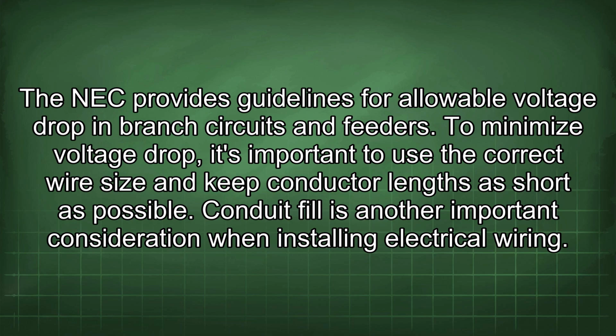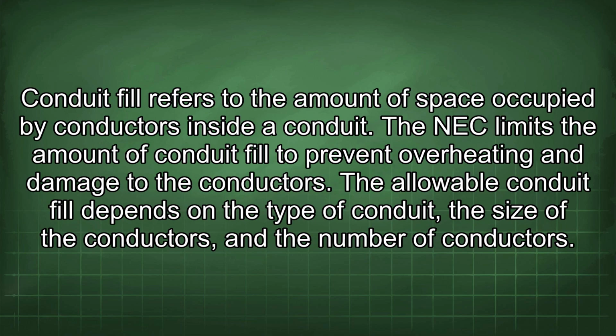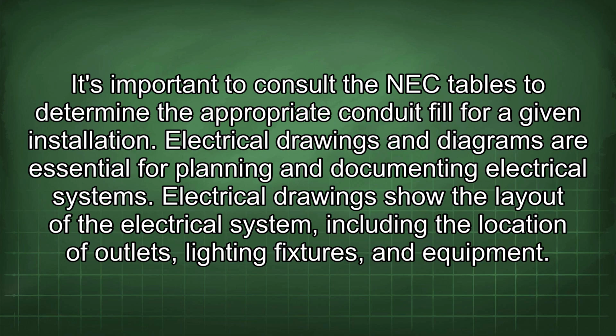Conduit fill is another important consideration when installing electrical wiring. Conduit fill refers to the amount of space occupied by conductors inside a conduit. The NEC limits the amount of conduit fill to prevent overheating and damage to the conductors. The allowable conduit fill depends on the type of conduit, the size of the conductors, and the number of conductors. It's important to consult the NEC tables to determine the appropriate conduit fill for a given installation.